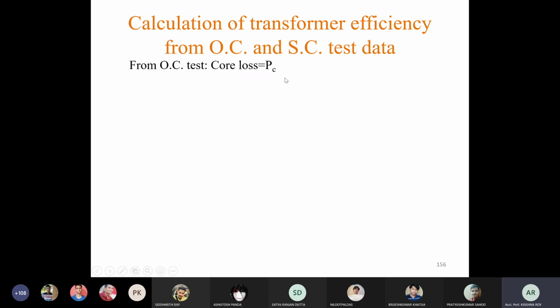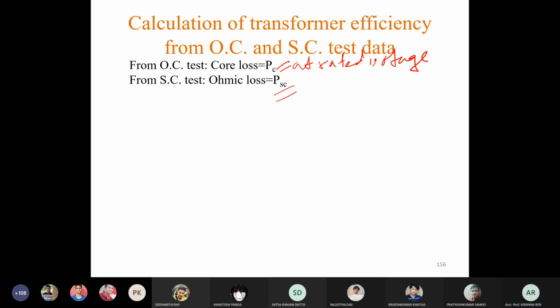From the open circuit test, core loss equals PC. From the short circuit test, ohmic loss equals PSC. Now the open circuit test is performed at rated voltage, so this PC is the rated core loss. Okay, no problem with that. But the short circuit test is sometimes performed at rated current, but it can be performed at other currents also. So this PSC may not be the rated copper loss. So you have to check whether it is the rated copper loss or not.